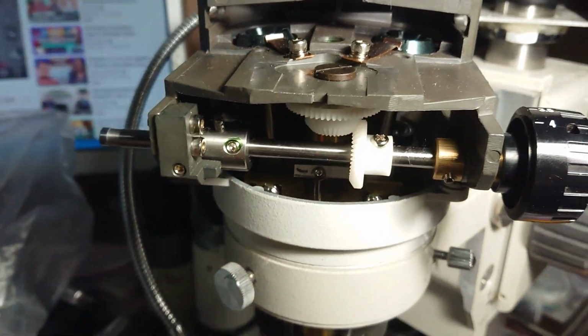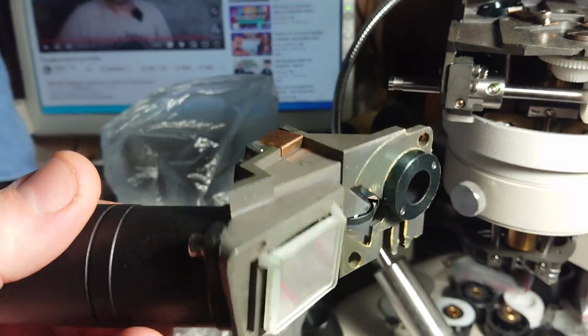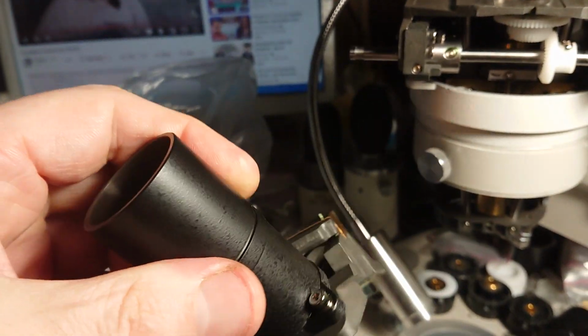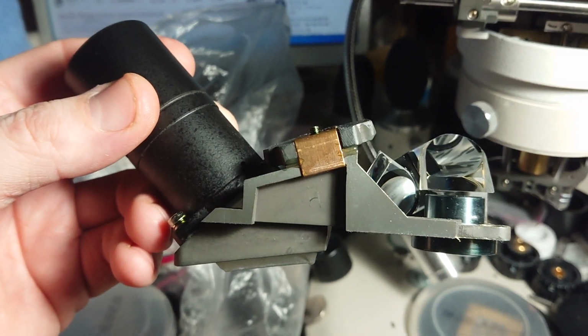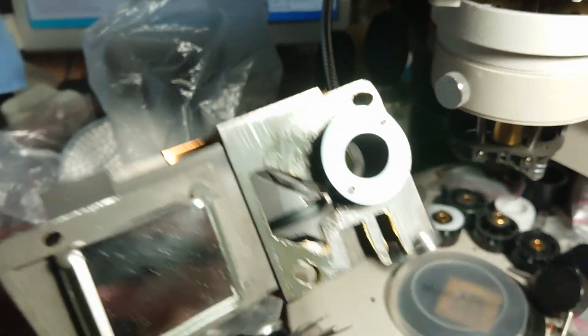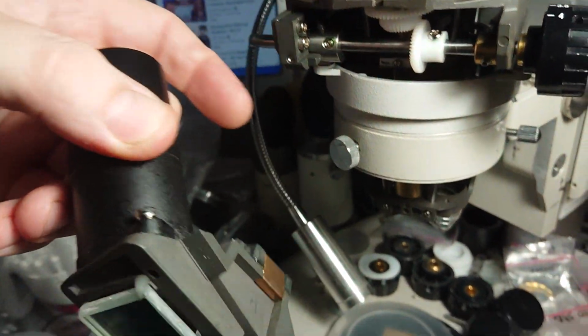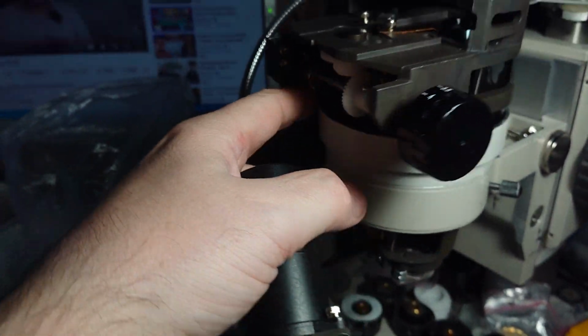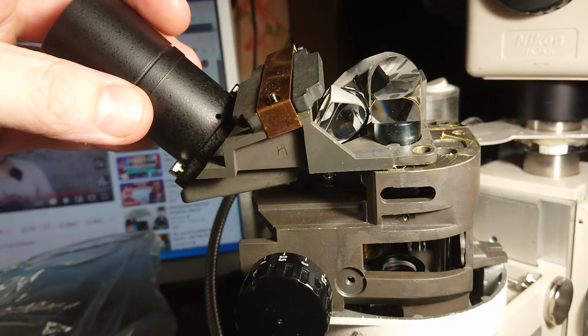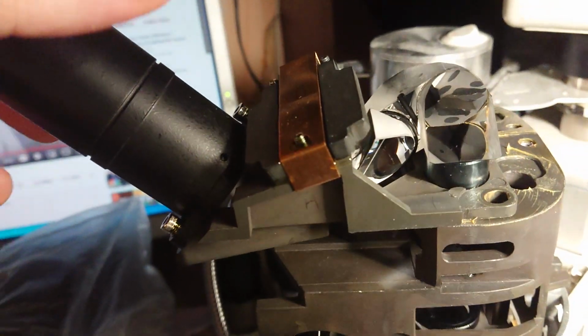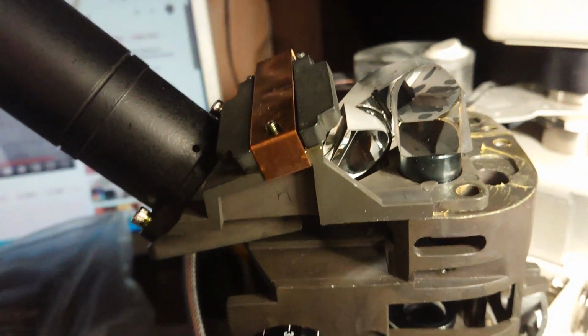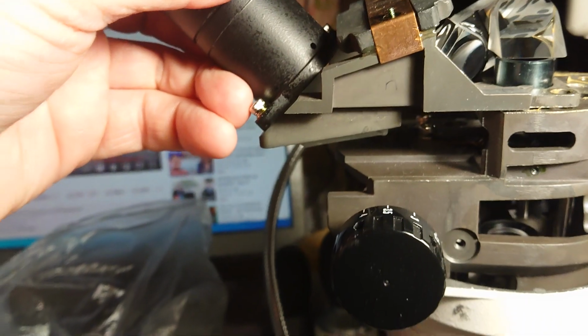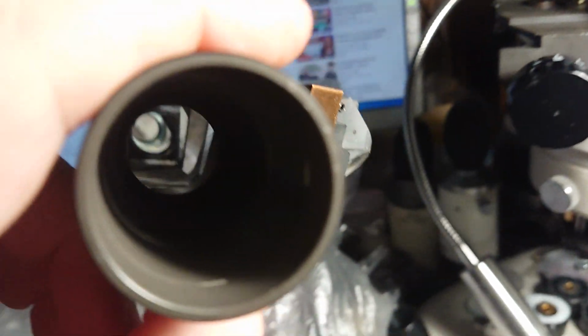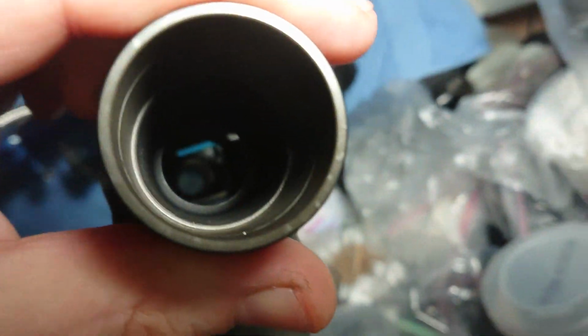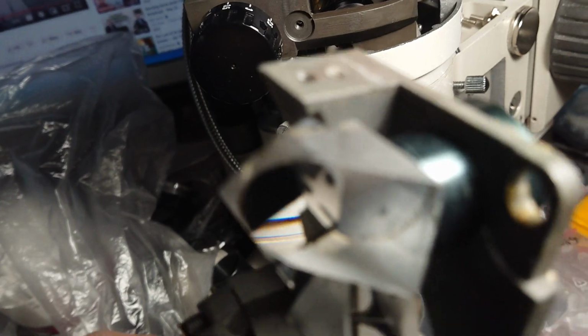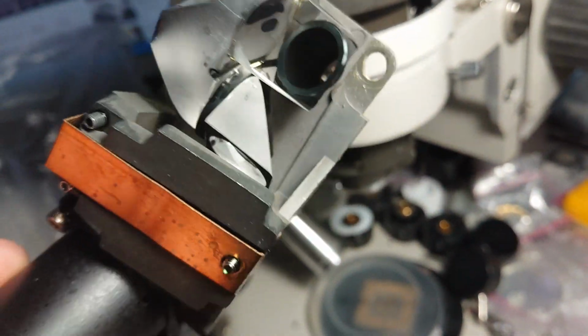So it's one part here, and the other part we are interested in is our erecting system with 45 degrees inclination. Our erecting system of the Nikon SMZ 745 consists of three glued prisms, after that we have two mirrors, and after that we have an eyepiece tube with protective glass. I have removed the protecting glass already, so no glass here.